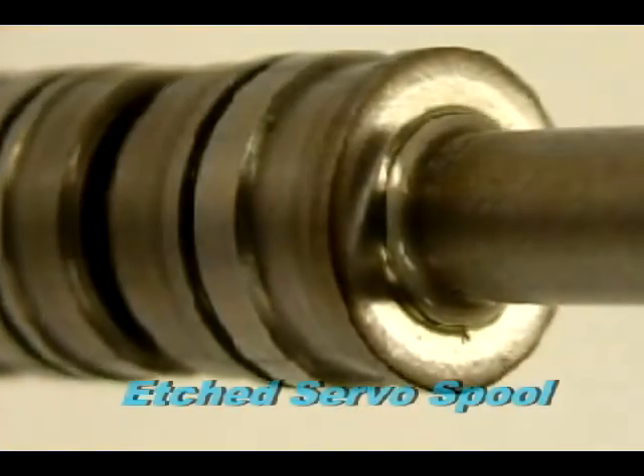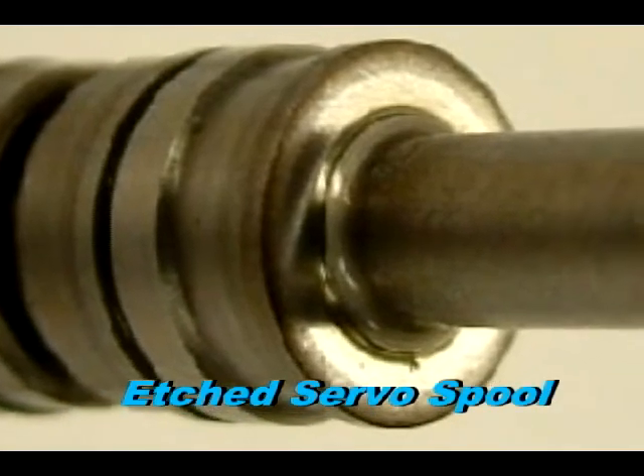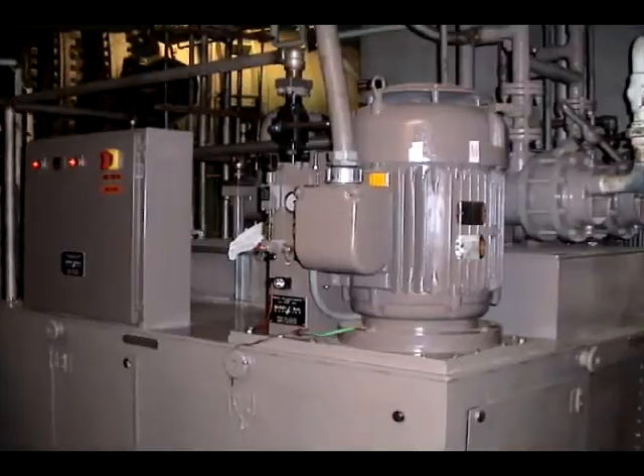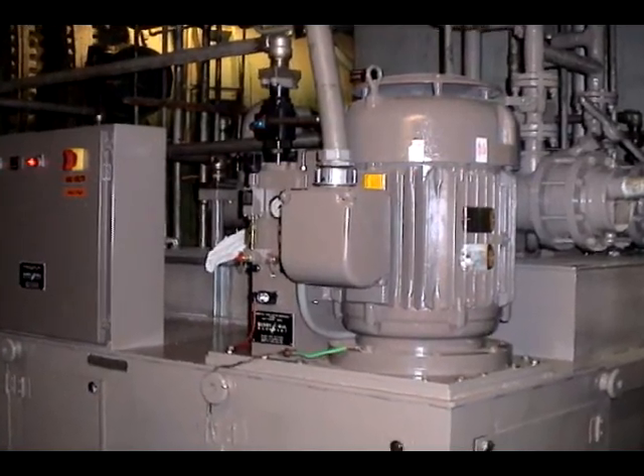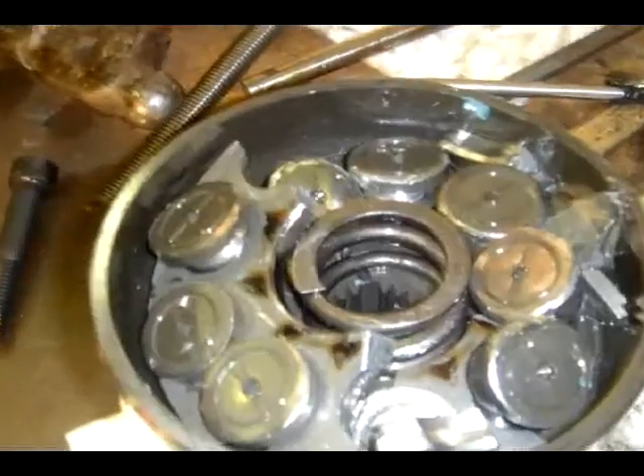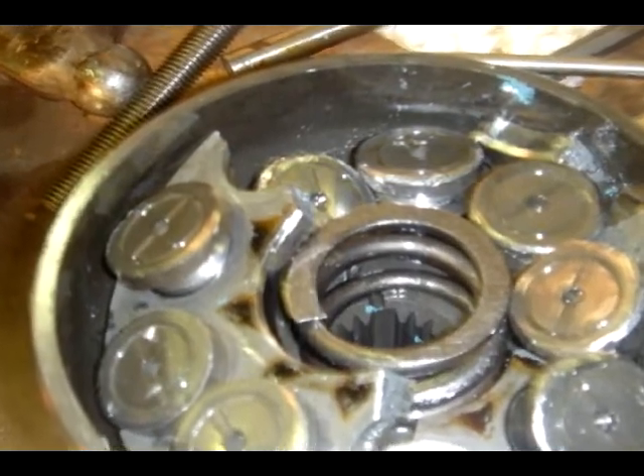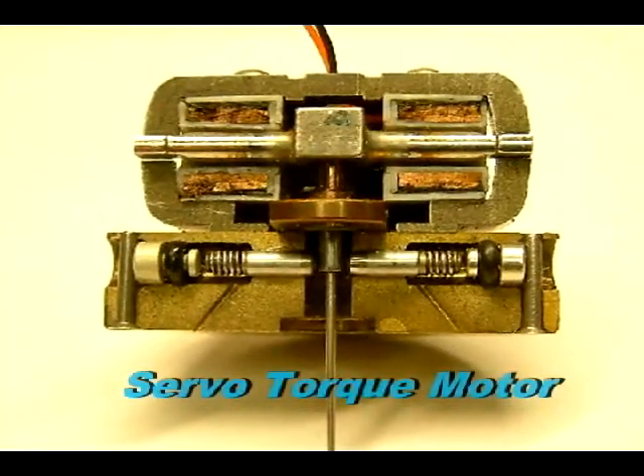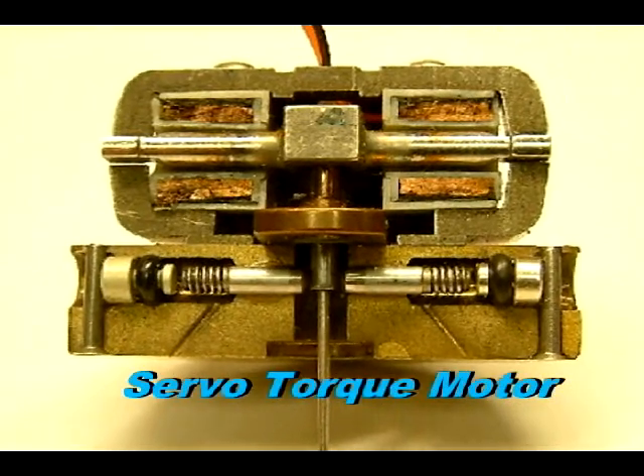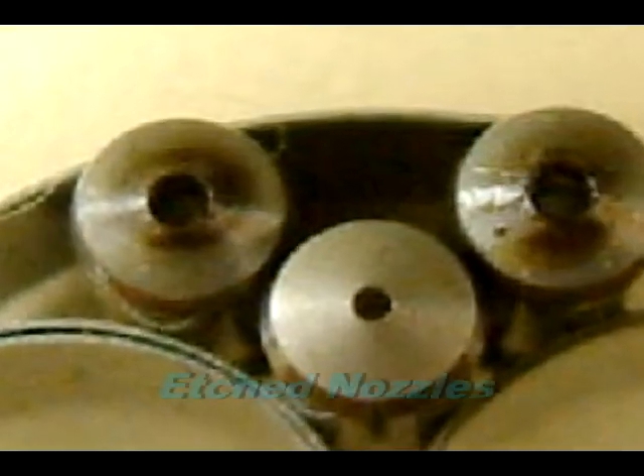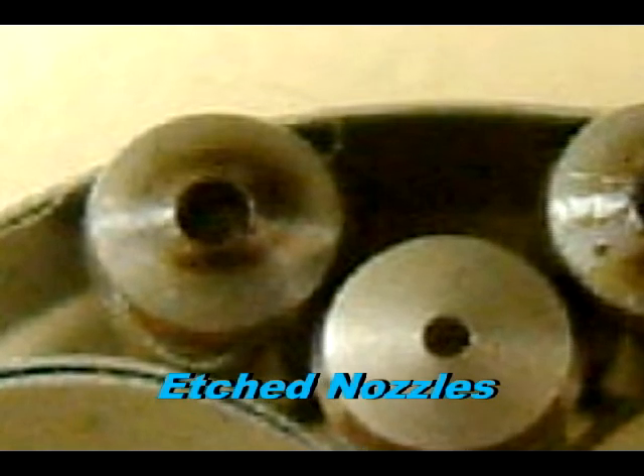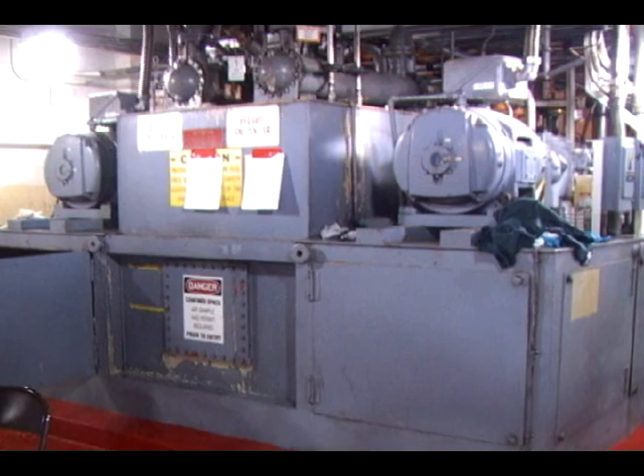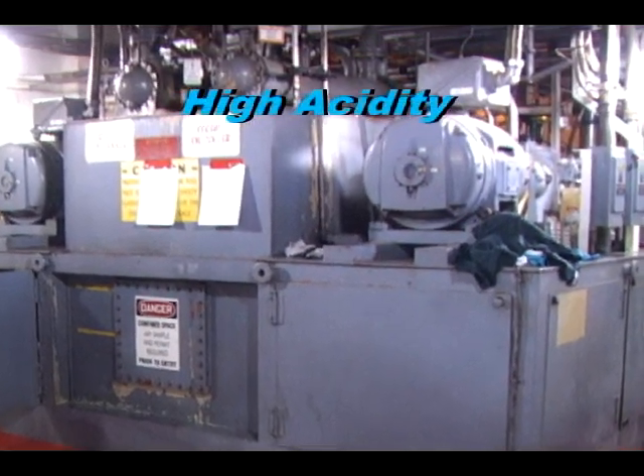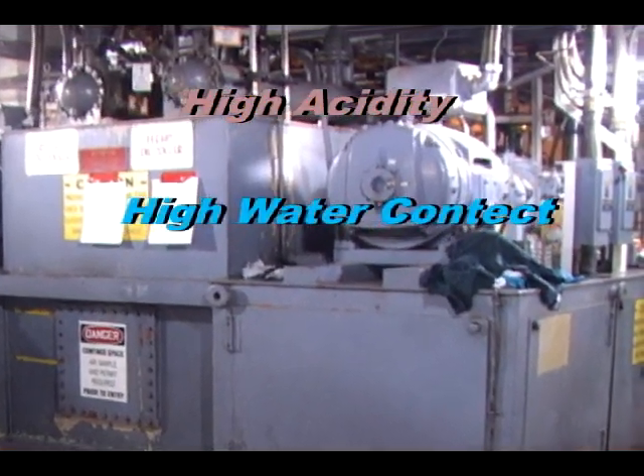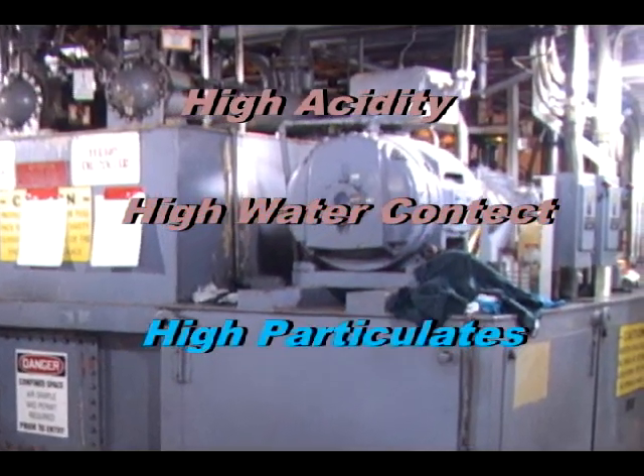The etching of the servo valve spools will cause increased flows through the servo valves. As these flows increase, the hydraulic fluid pumps work harder and can ultimately experience premature wear of their internals, causing pump problems. In some servo valves, the etching can cause problems with the torque motor nozzles, causing the servo valve to respond erratically or in some cases fail to the closed position and remain there. The cause of low resistivity in FRF has been directly related to high acidity, high conductive water content, and high ferrous particulates in the fluid.